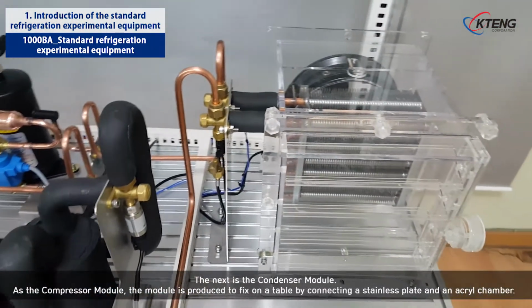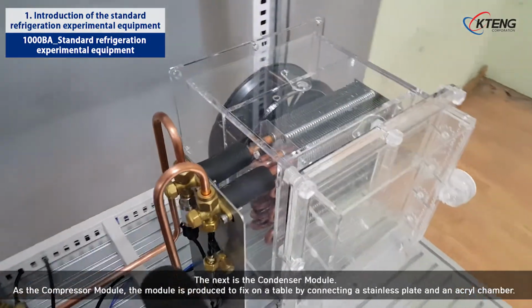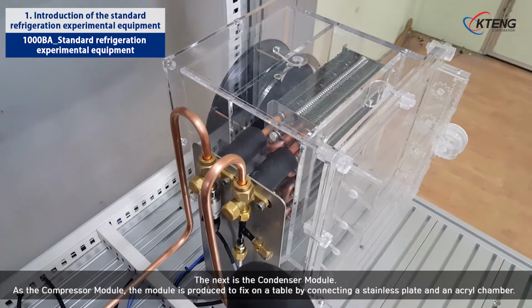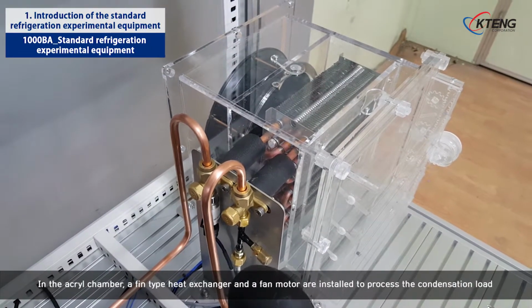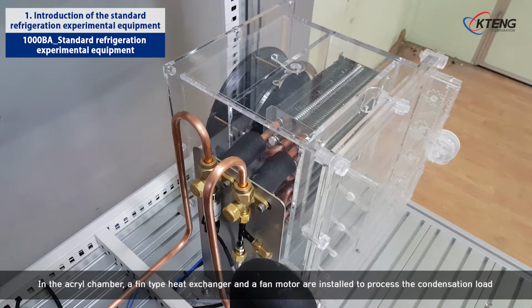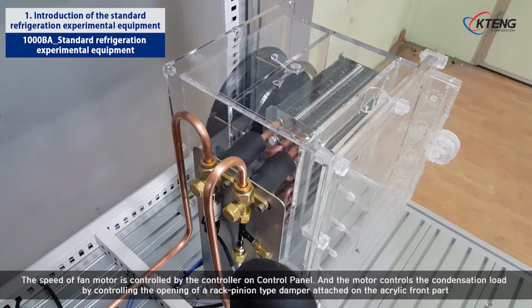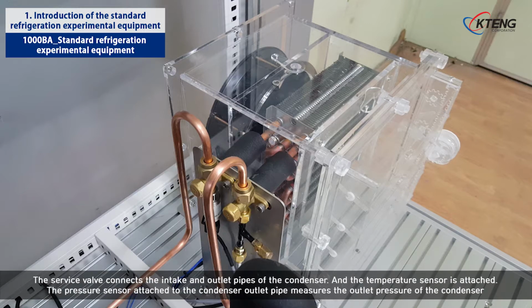The next is the condenser module. As the compressor module, the module is produced to fix on a table by connecting a stainless plate and an acryl chamber. In the acryl chamber, a fin-type heat exchanger and a fan motor are installed to process the condensation load. The speed of the fan motor is controlled by the controller on the control panel, and the motor controls the condensation load by controlling the opening of a rack pinion-type damper attached on the acrylic front part. The service valve connects the intake and outlet pipes of the condenser, and the temperature sensor is attached. The pressure sensor attached to the condenser outlet pipe measures the outlet pressure of the condenser.